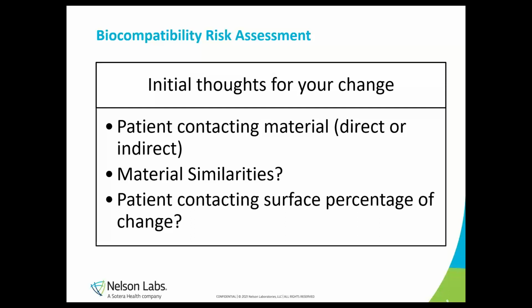Polymers tend to have a little bit more risk associated with them, even if you're using the same type of polymer. The other thing that's important to do, and a lot of people don't think about this, but from a biocompatibility perspective, it's all about dose to the patient. So the size of the patient contacting change is very important. If you have a very big tubing set, for example, and you're changing just a very small component of a stopcock, for example, that change to the overall biocompatibility risk of that tubing set could be pretty low.